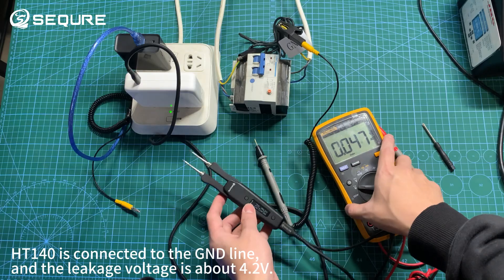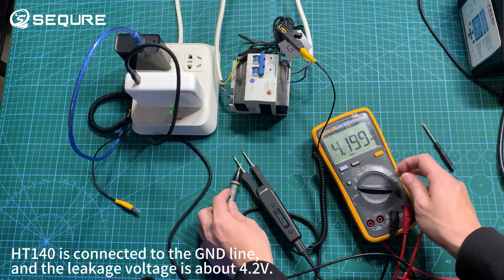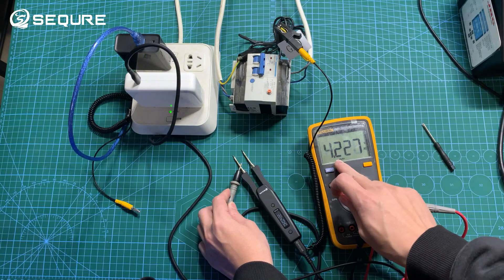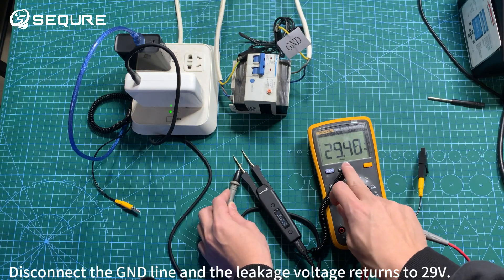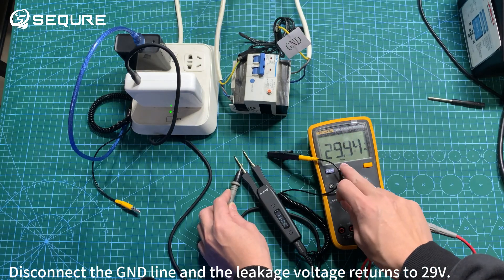When the HT140 is connected to the GND line, the leakage voltage is about 4.2 volts. Disconnecting the GND line causes the leakage voltage to return to 29 volts.